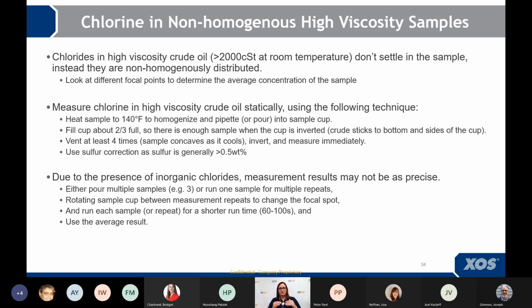The other thing you want to note is, because you've heated this sample up, what happens as the sample cools is the film, which is flat, will concave. Without that flat film surface, you don't get an accurate measurement. It'll actually bias low because it changes the focal point. So what you do is you vent the sample at least 4 times, as this will keep the film from concaving. Then you go ahead and measure that immediately. Don't forget to use sulfur correction, as these types of samples generally have sulfur in excess of 0.5%.